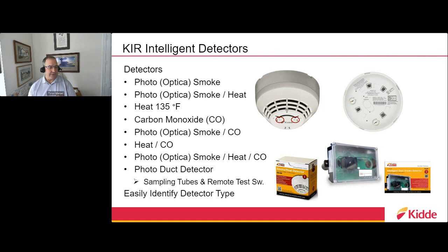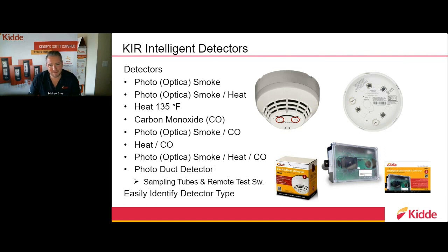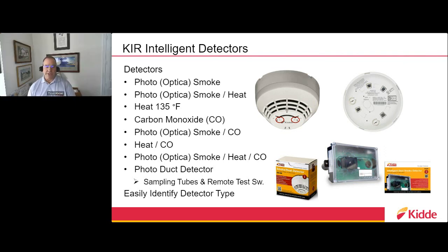I also want to highlight the easy identifiability. As you can see on the screen, there are two small red circles under the image of the smoke detector. One circles an O, indicating Optica technology, and the other circles an H for heat. So a person standing on the floor could view it and understand that it's a combination unit doing smoke and heat. Like all our Kidde field devices, these use a rotary dial, so addressing the devices in the field is very simple and easy.